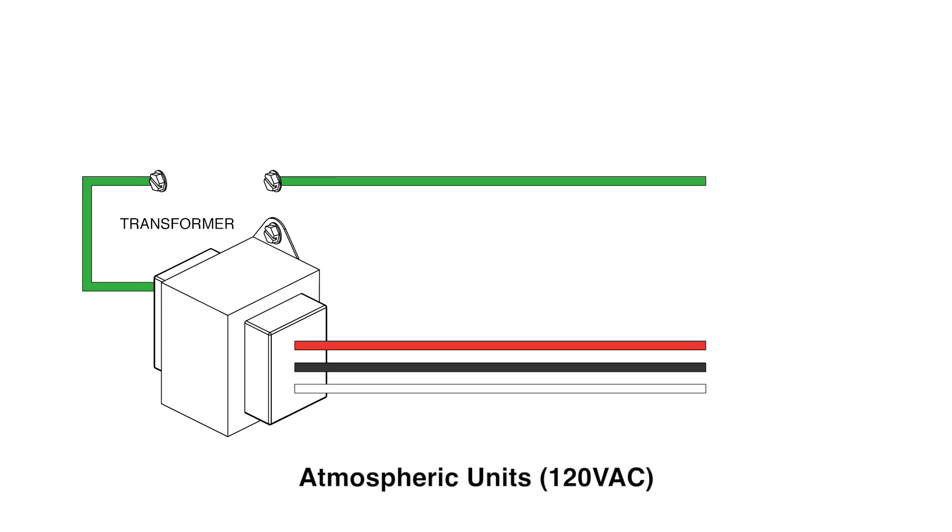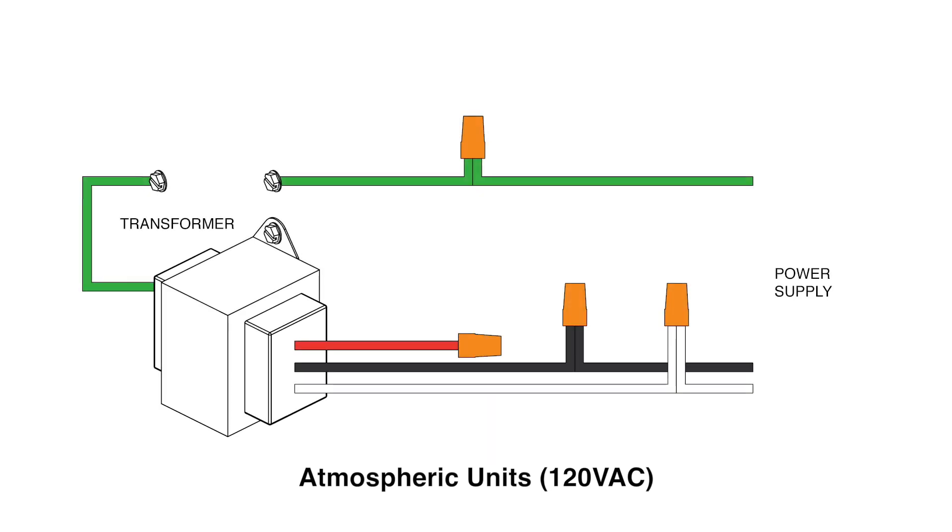For 120 volts, strip back the ends of the incoming wires as well as the black, white, and green wires from the transformer. Attach the incoming hot wire to the black wire from the transformer using a wire nut. Attach the incoming white or neutral wire to the white wire from the transformer. Attach the green ground wires.